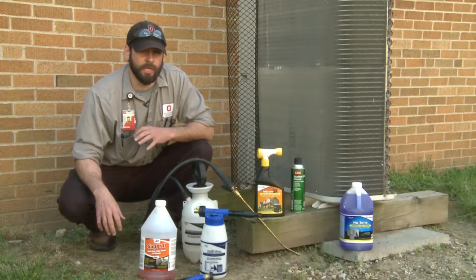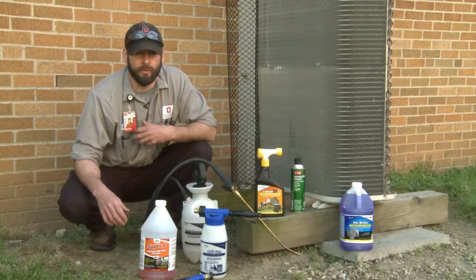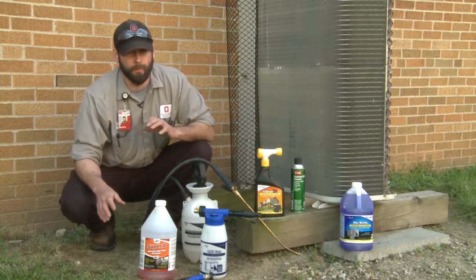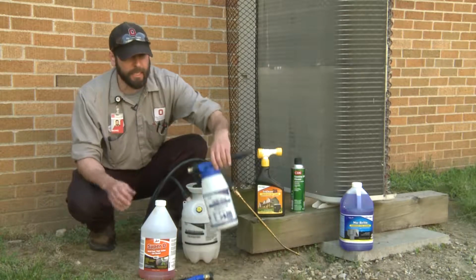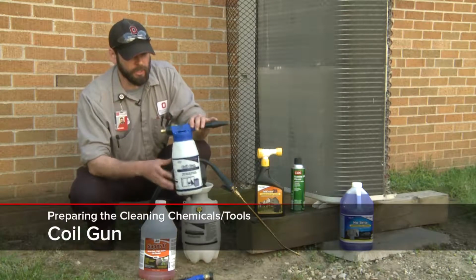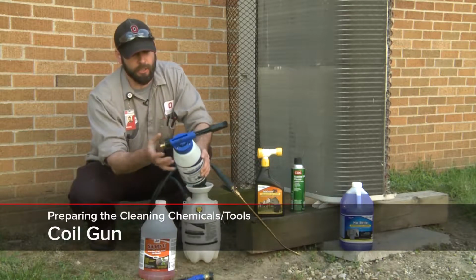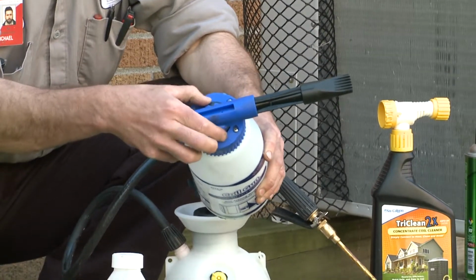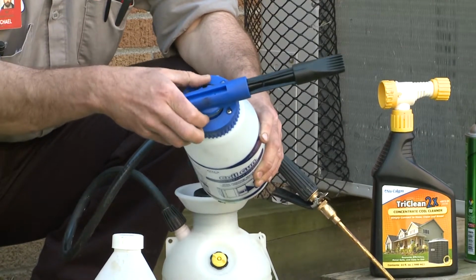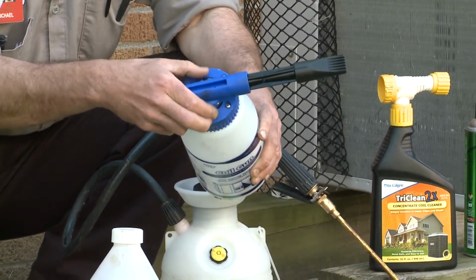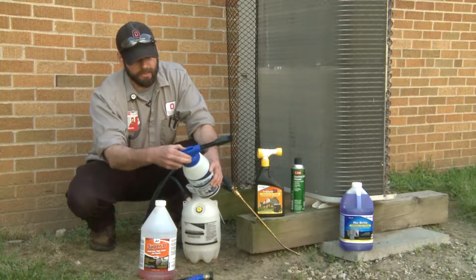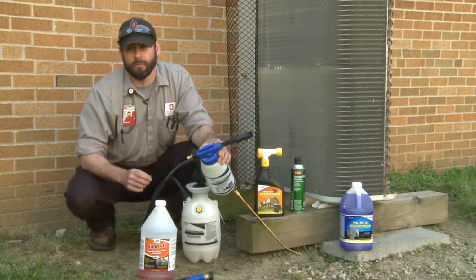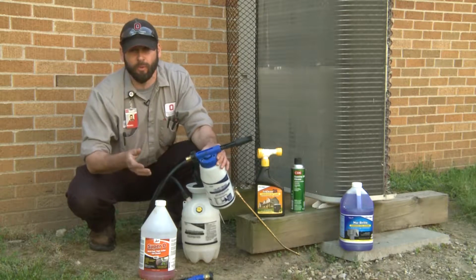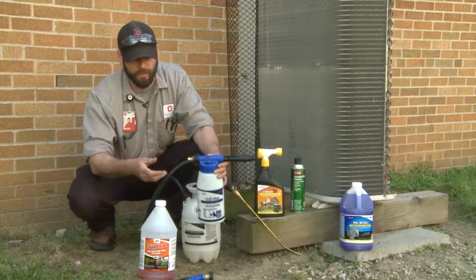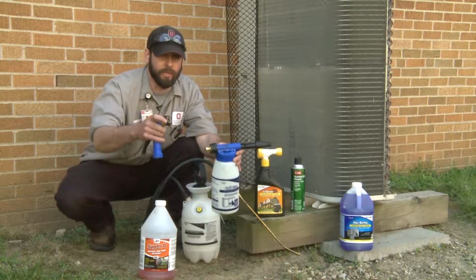Okay, so there are a couple of different ways to apply our chemical to our various coils. My preferred method, and the one we will be using today, is a coil gun. The coil gun has a set ratio that is adjustable on the top with settings A, B, C, and D, A being the highest ratio and D being the weakest. It also has a straight water option for just rinsing your coil, so you don't even have to take the gun off of the hose connection. It has a quick connect hose nozzle.